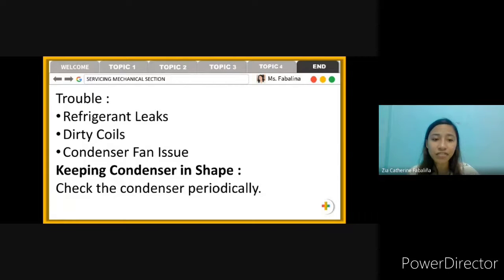Next is condenser fan issue. The condenser fan helps transfer heat from the refrigerant system into the outdoor air and prevents our compressor from overheating. The condenser fan has trouble because of some reasons like when the capacitor overheats, runs too long, or the aircon is already too old. So the condenser will no longer operate.